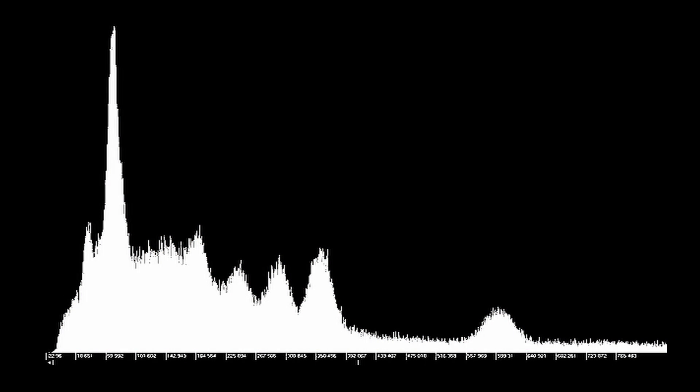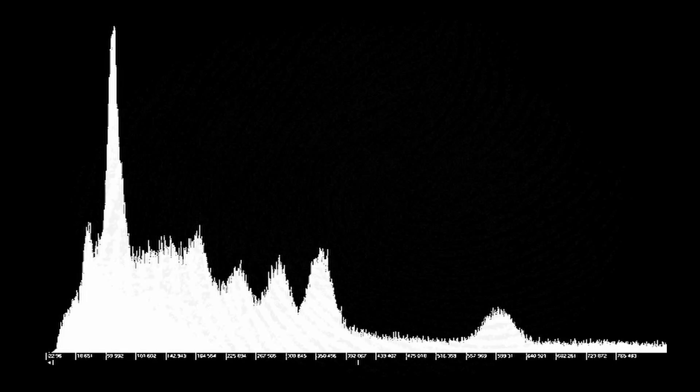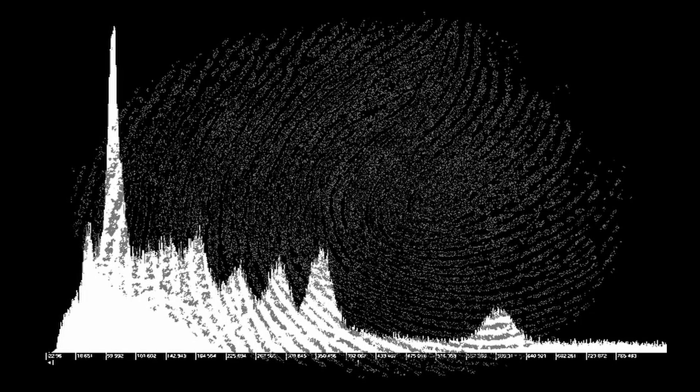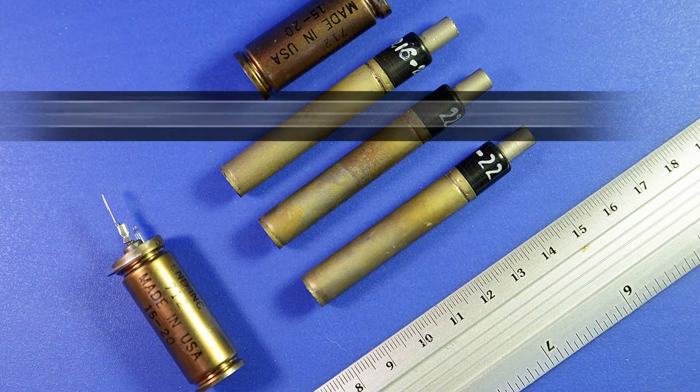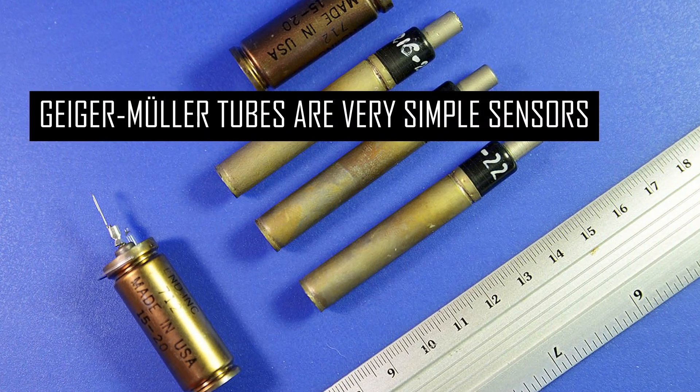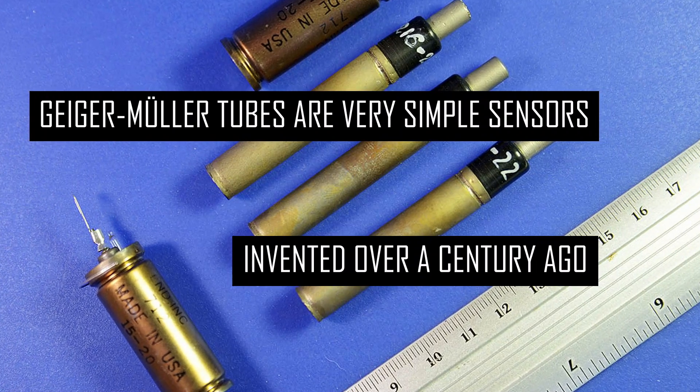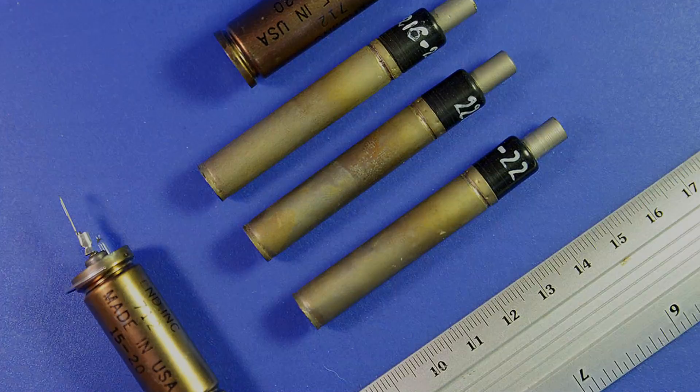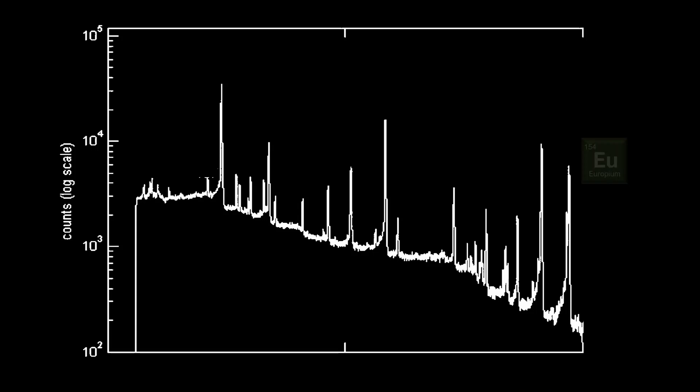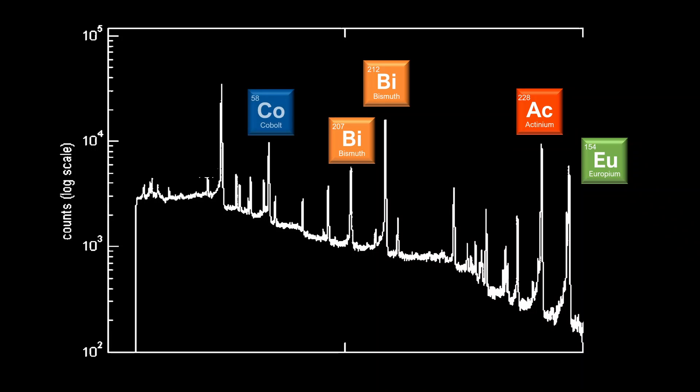Because a spectrometer knows not only how many gamma rays it has detected, but also the energy level of each one, it can construct a fingerprint of the radiation it is exposed to. A Geiger counter, for example, can only count how many rays it has detected and obtains no information about the actual energy levels involved. Being able to create a fingerprint of the spectrum of the radiation means that a gamma-ray spectrometer can actually identify the radioactive materials that it is exposed to.